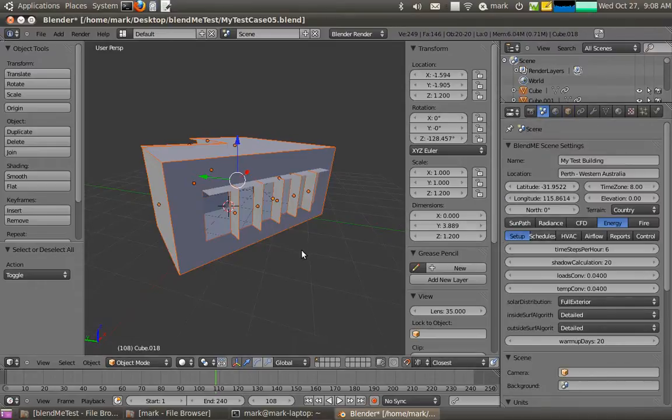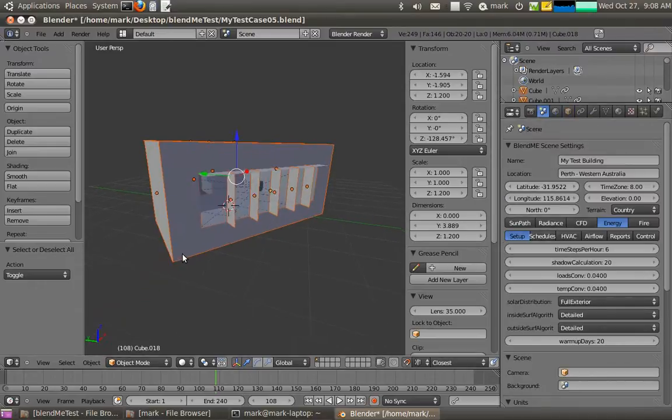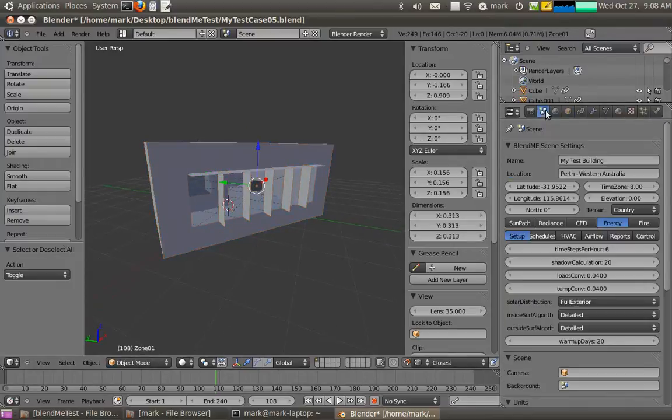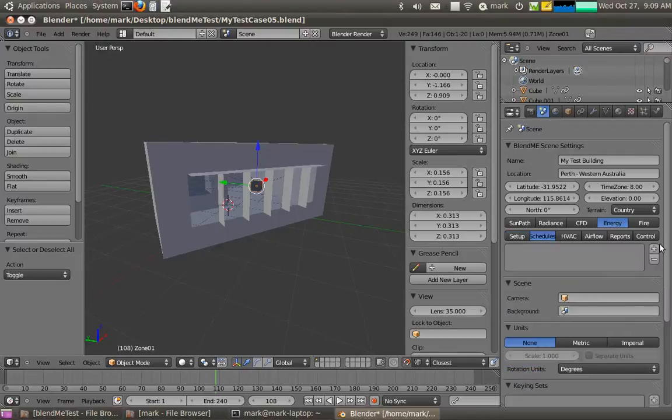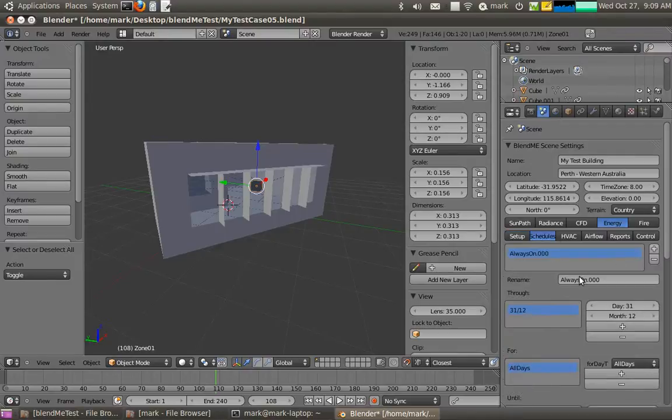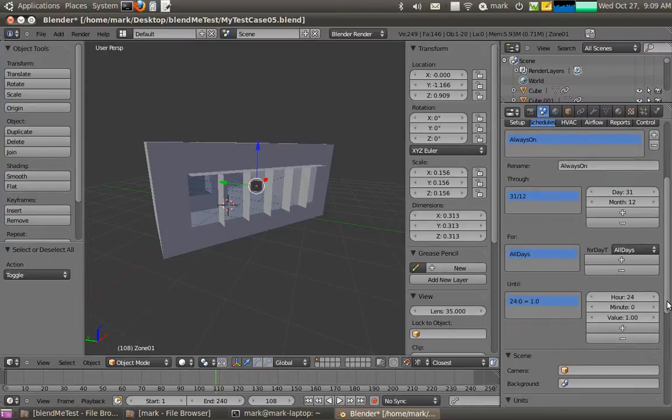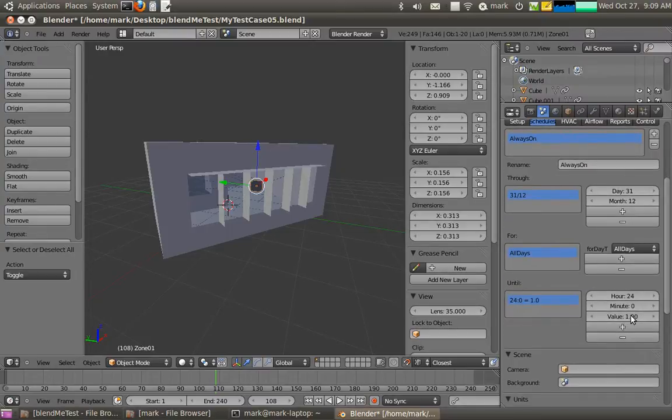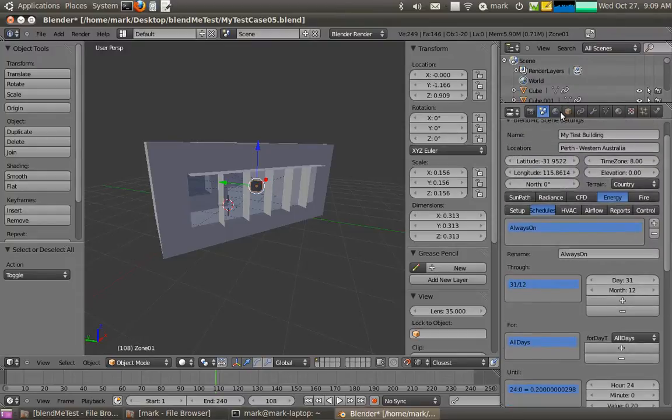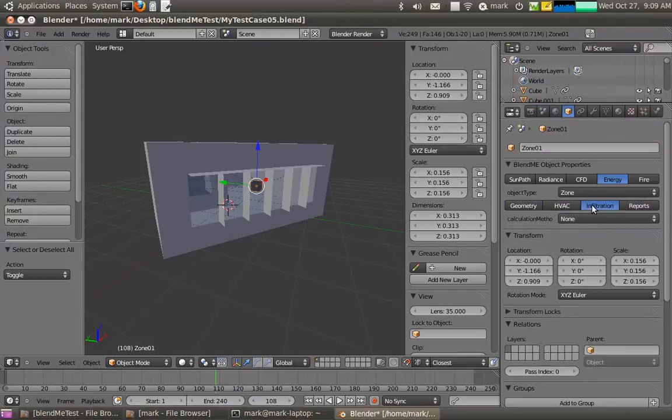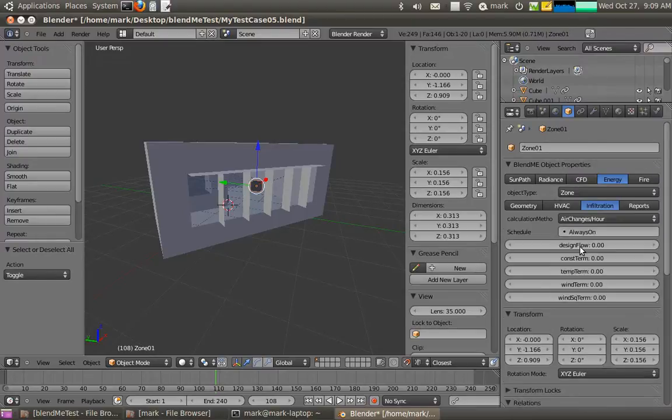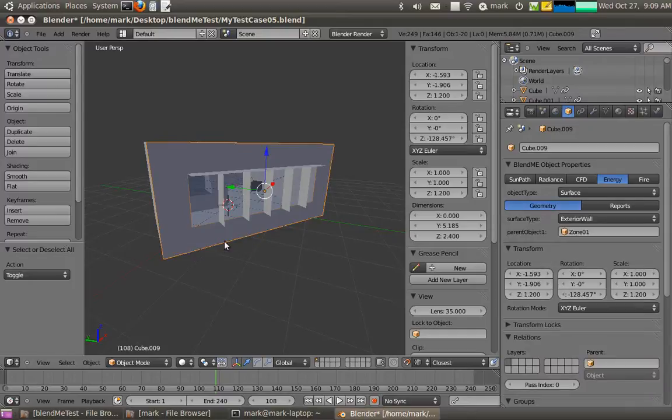So what I have to do here is go back and actually create a schedule, and I'll call it, by default it's always on, so I'll call it always on, 0.2 air changes per hour. And if I go back to the object menu infiltration, I can actually assign it always on, 0.2 in there as well.